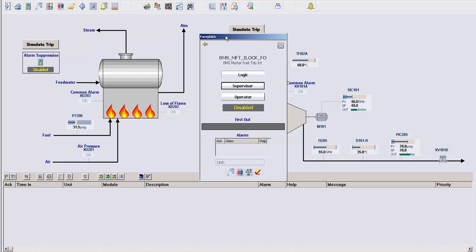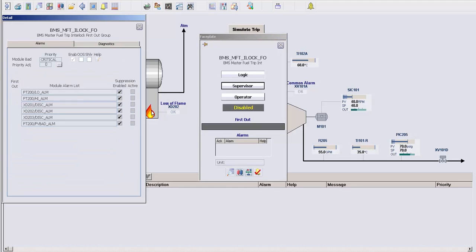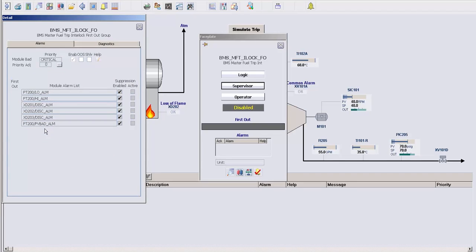If we look at the detailed faceplate here, you'll see that this module allows you to specify up to 16 alarms that you want to consider as part of the alarm suppression. The idea here is that if one of these alarms occurs, the remaining alarms in the list will be suppressed.